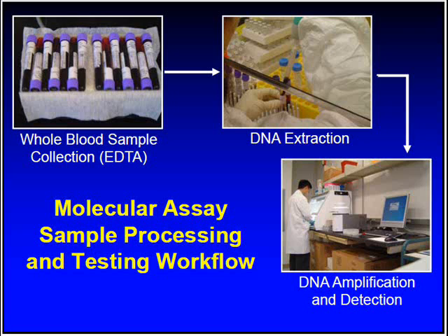Post-processing of the data is by software. With the SeptiFast method, the total analysis time from sample arriving at the lab to reporting a result is about 6 hours when we are simultaneously batch testing 7 patient samples.